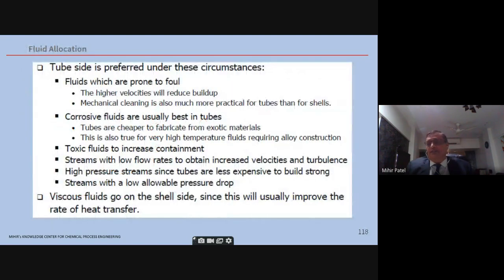Now fluid allocation. This has to be done by the process engineer. It's very important. The tube side is preferred under these circumstances. Fluids which are prone to foul because you can clean them very easily. Corrosive fluids best in tubes because your tubes will be cheaper. The shell side material is not affected. Then toxic fluids to increase containment.